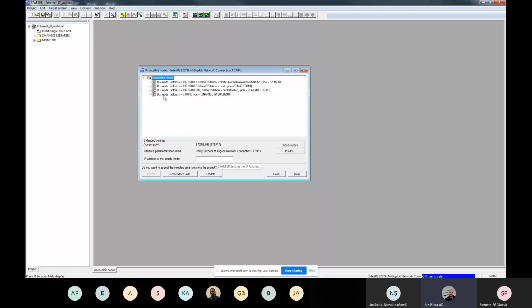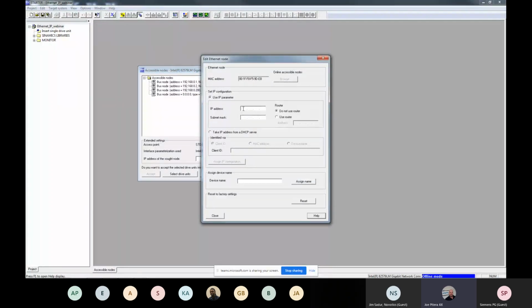Okay, so we have found this bus node with an illegal IP address of 0.0.0.0. It is a Sinamics G120 CU240. If you right click on that and edit the Ethernet nodes, we are going to give this an IP address. For my demonstration here, I am going to give it the IP address of 192.168.0.11, with the standard subnet mask of 255.255.255.0. I am going to assign the IP configuration to the drive. It told me it was transferred successfully.